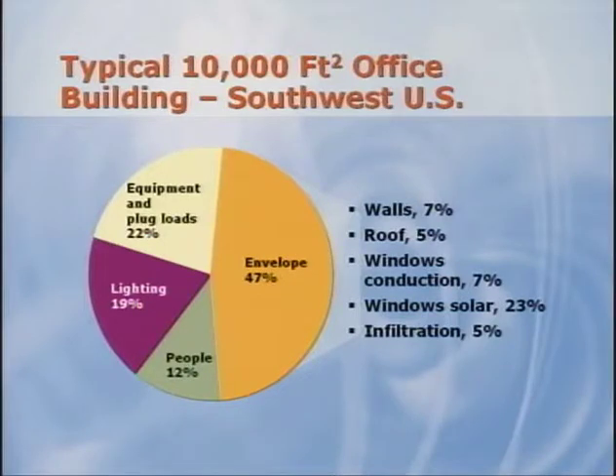The purpose of this example is just to show for our discussion that the building envelope and other internal loads can contribute to a large percentage of the building load. Looking at the data, we see that 23% of the entire cooling load has been created by the solar load through the windows. You might be thinking, where did this data come from? The simple answer is from modeling the building. Most modeling tools have excellent reporting capabilities that give engineers a large amount of information pertaining to the building modeled. Understanding and using this information can give you the opportunity to lead a discussion with the rest of the building design team and possibly recommend to the architect other window glazing or shading options be considered.